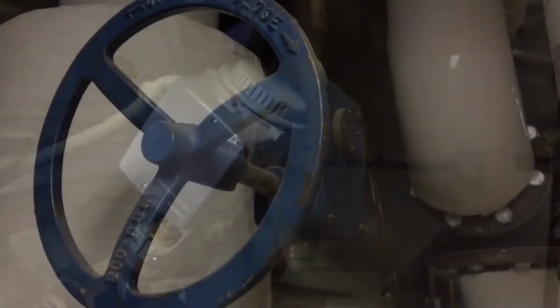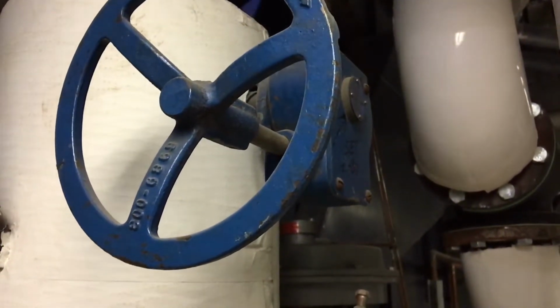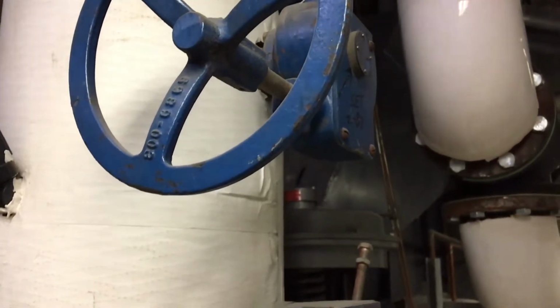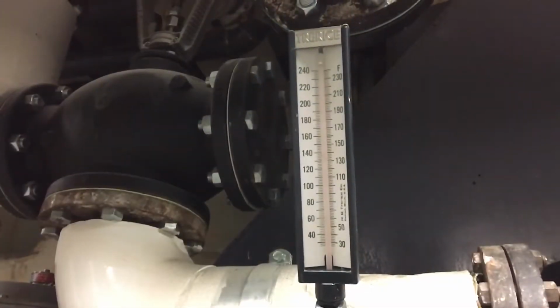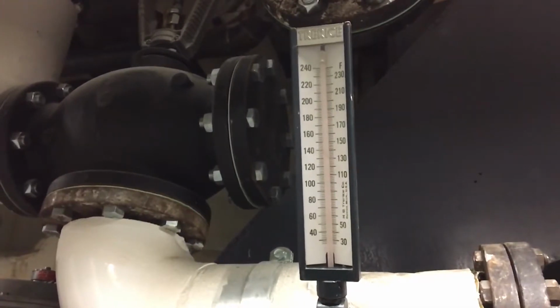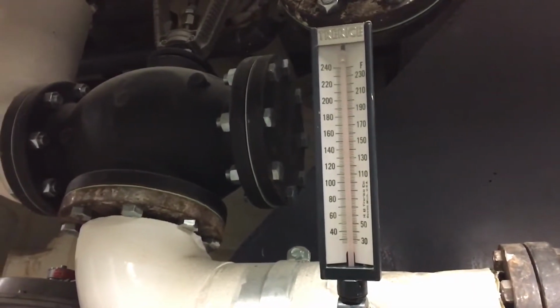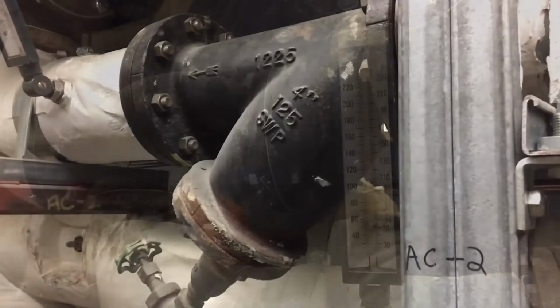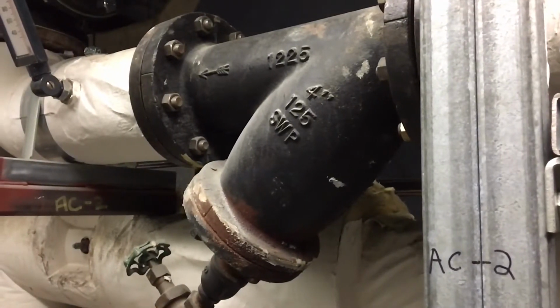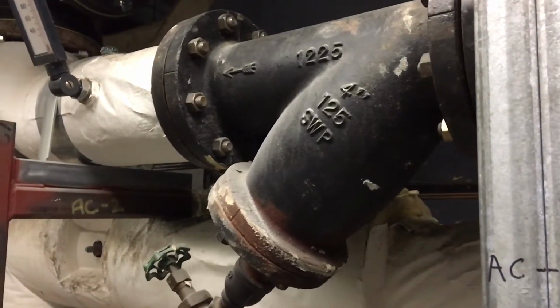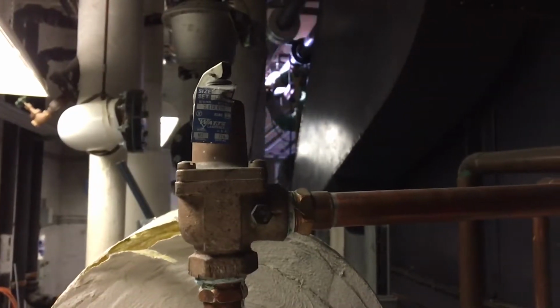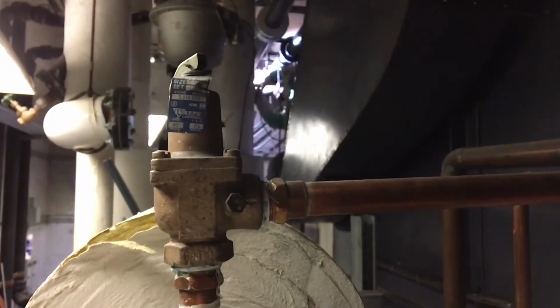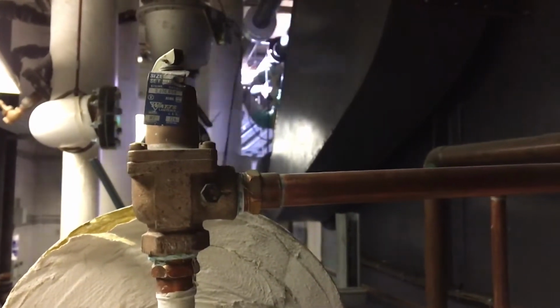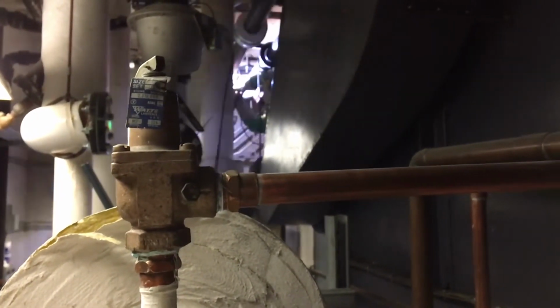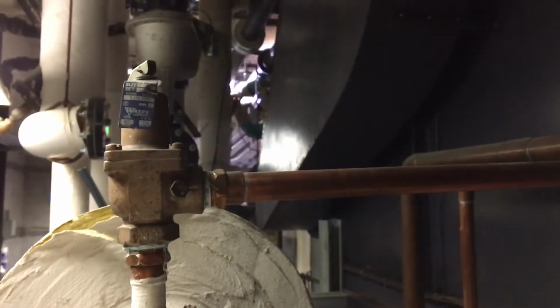A hydronic piping system is not only comprised of pipe and fittings, but also has other important components and accessories as well. The components shown are located on the secondary loop of this building's hydronic system. Temperature and pressure gauges are installed to easily monitor the operating condition of the system. The Y strainer is installed to catch any particles or debris in the heat transfer fluid from re-entering the system. A pressure relief valve is an automatic pressure relieving device actuated by the static pressure upstream of the valve, and it opens further with the increase in pressure over the opening pressure.